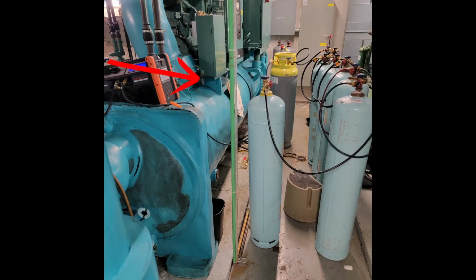So what's happening is I'm pulling vapor off the chiller, from the refrigerant that's already been charged, and pushing that vapor back into this cylinder. As that happens, it pressurizes the cylinder and pushes the liquid down, which draws it into the next tank. Keep in mind, since I'm pulling vapor off the chiller, there's also a pulling action happening, not just pushing. Those two effects combined literally pushed all that liquid refrigerant through each tank until we had completely charged every one with just a single hookup.